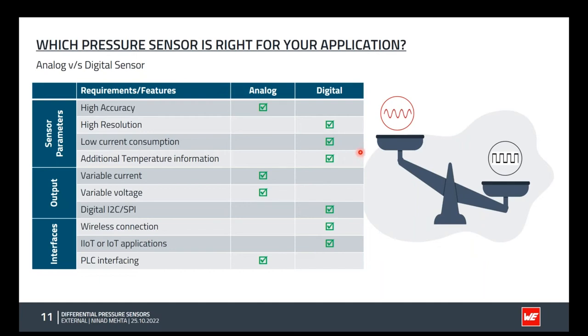But on the other hand, if some application requires variable current output or variable voltage output, then purely analog sensors need to be used. And for applications which require wireless connectivity or cloud connectivity, where your sensors directly send the data to a wireless module, it's better to have a digital output, so that you have a kind of plug and play system where it's very easy to connect the sensor to the wireless module and have access to the data remotely.